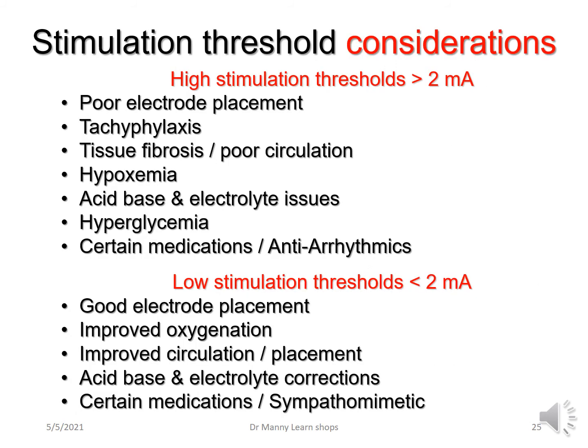Stimulation threshold considerations — when things don't go according to plan: high stimulation thresholds, more than 2 mA, typically occur because of poor electrode placement, tachyphylaxis — meaning the heart has adapted and requires higher and higher doses of stimulation — tissue fibrosis or poor circulation where the electrode is placed, hypoxemia, acid-base and electrolyte issues, hyperglycemia, and certain medications such as antiarrhythmics like amiodarone that decrease sensitivity.